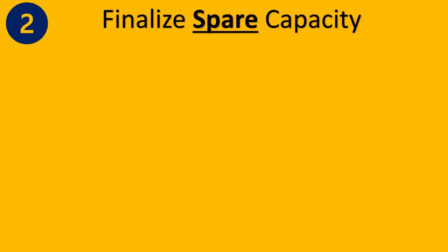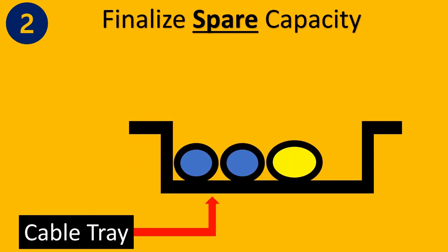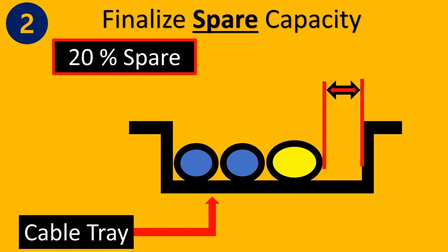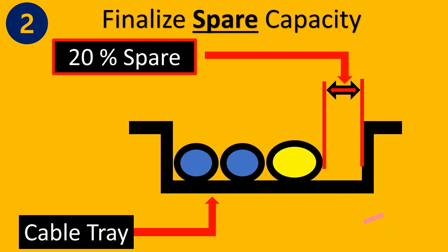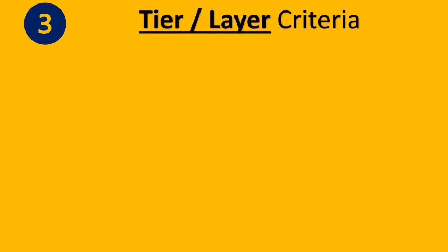Step two is finalizing the spare capacity. No matter how well you size your cable tray, some calculations might have been missed or space may be needed for future expansion. You need to keep a certain portion empty — this is called spare capacity, which is usually 20% or 30%, depending on whether it is a FEED or detail engineering project and what the client requirement is.